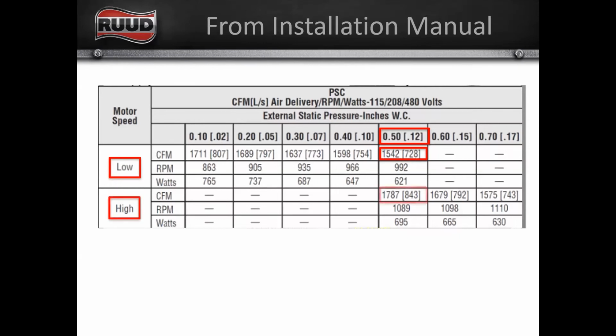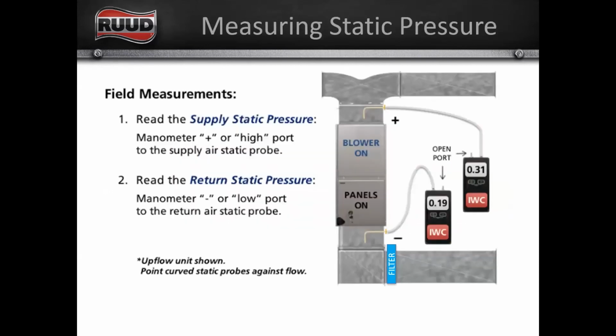If we are on high speed, we're moving 1,787 CFM. And the difference between these two is whether we're on low speed or high speed. So that's the other thing that we have to know: what's our blower speed. We could also measure this if you had a single port manometer, right? Or like I mentioned, it's usually a good idea to check your supply and return. A lot of electronic manometers will allow you to cycle through to display your positive and your negative, or tap A and tap B, or however they have it set up or displayed. So you can see, again, we got the same numbers, right? We have a 0.31 on our supply, we have a 0.19 on our return.